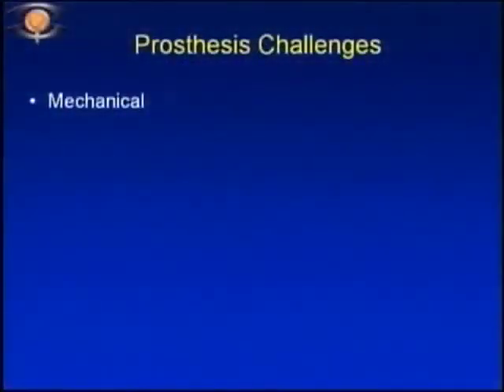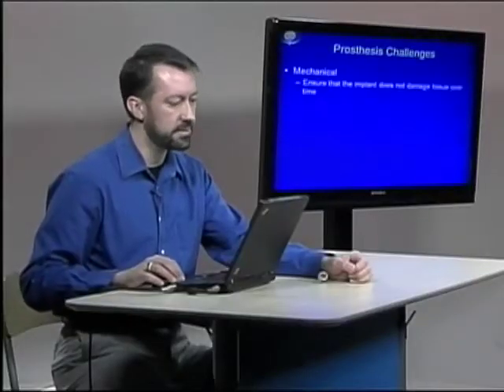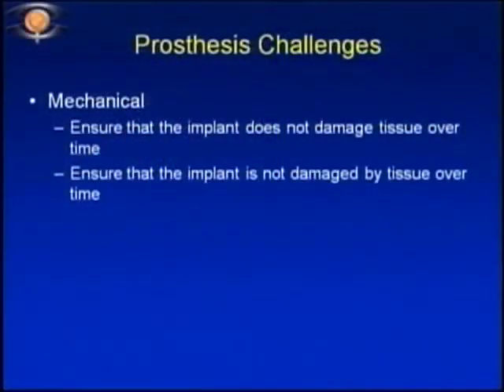So the final set of challenges that we're going to discuss are mechanical challenges. When you place a device in the body, not only can it cause biological challenges, not only can the materials cause biological reactions, but mechanically you can design a device that when it moves around in the body damages the body mechanically. Obviously we need to protect against that. So we need to ensure that the implant does not damage tissue over time and that the implant device is not damaged by tissue. If you have an electrode or a lead that's very thin in a body part that's moving, that lead needs to be flexible enough that it can flex tens of thousands of times without failing, without causing damage to the implant itself.